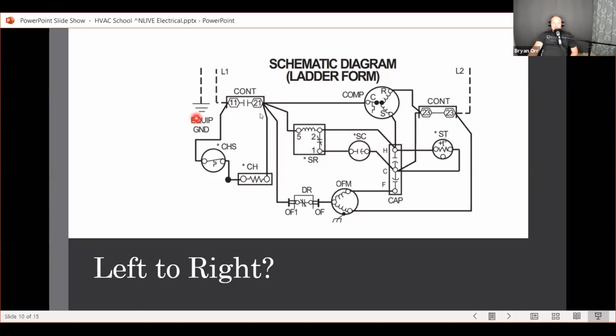It works because when this switch is closed, this is a good way, because I like to talk about a voltmeter as a voltage drop measurement tool. It's a way to think about a voltmeter that's helped me a lot as I've gotten more and more comfortable with a voltmeter through my career. When this contact is closed, if I connect one side of the voltmeter to 11 and the other side to 21, what am I going to measure? I'm going to measure 0 volts or thereabouts.